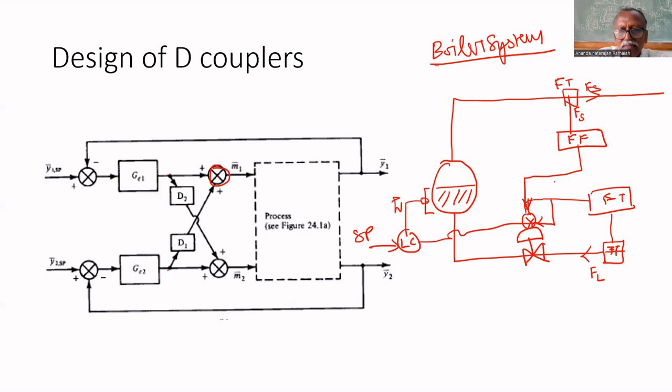If there are any changes in that, it will adjust the valve opening to increase the inlet flow rate. In addition to that, the level control feedback controller is there that adjusts this valve. This is the boiler system with the conventional as well as feed forward controllers that we have seen. So all the three: this is feed forward 1, feed forward 2, this is the feedback controller. So all are added together to adjust this valve.